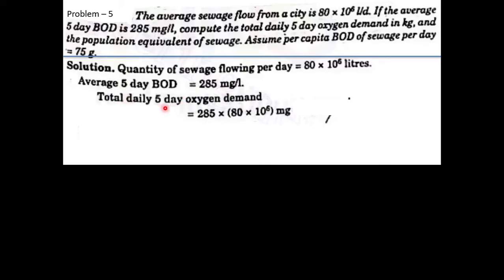Given: flow = 80 × 10^6 liters/day, average 5-day BOD = 285 mg/L. Total daily 5-day oxygen demand = 285 × 80 × 10^6 = 22,800 kilograms.